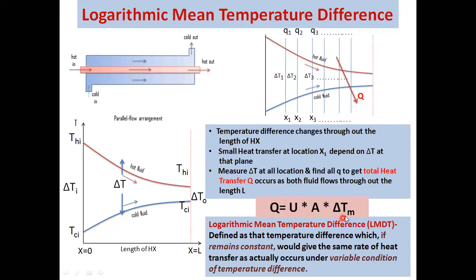So for that we define a term called the logarithmic mean temperature difference. The temperature difference changes throughout the length, and the heat transferred from hot fluid to cold fluid at any section depends on the local temperature difference. In order to get the total heat transfer across the heat exchanger, we need to sum up all these small heat transfers taking place at each section, which depend on the local delta T. So to calculate the total heat transfer, we devise a term called LMTD.